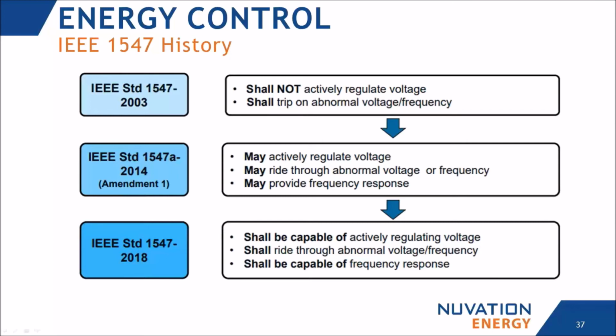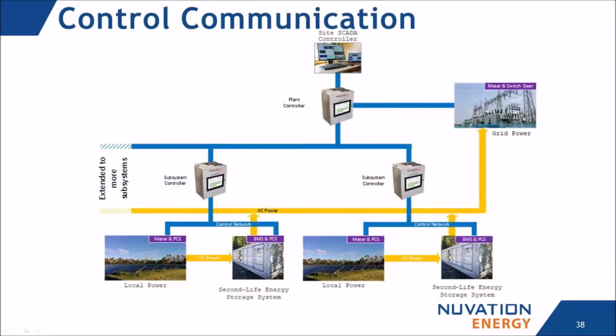You must provide these high functioning services using this standard whenever you're deploying to the grid. So I want to come back to this diagram I've been showing before and really discuss what it means. It means that you should have a layered approach to your control. If you're talking IEEE 1547, it's mostly in this area at the top layer here, just before, as you're connecting to the grid. That's the implementation point for the standard.